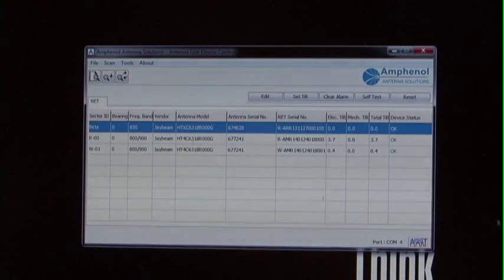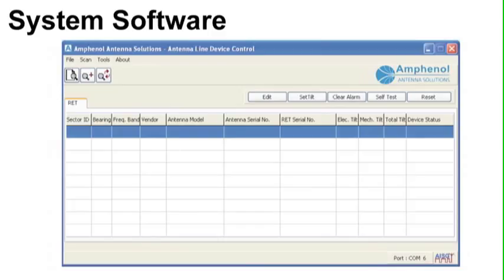After a scan, the main screen will show a number of attributes: the device name, sector ID, bearing, which is the antenna bearing in the range from 0 to 359 degrees, the frequency band, the vendor name, the antenna model, the antenna serial number, the RET serial number, the electrical tilt value, any mechanical tilt value, the total tilt, which is the sum of the mechanical tilt and the electrical tilt, and the device status. The device status will show an OK or a device alarm message if there is a problem.